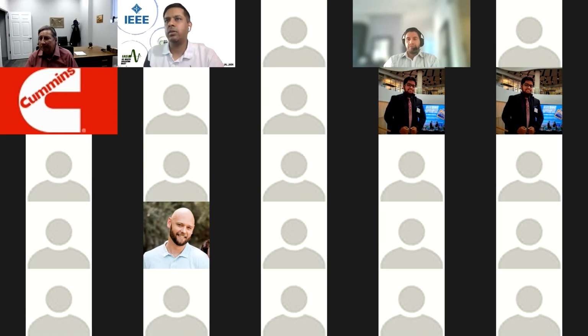Yeah, I have one comment from Mr. Matsuda again. He said, while passive filters are low cost, their LC component is fixed, usually tuned to 100% speed of the VFD/motor. Active harmonic filters are higher cost, but they mitigate harmonics through all loading or speed combinations and provide power factor correction. Okay, good question. I think I understand some of what he's looking at there. Truly, an active harmonic filter does cover the load range very effectively. Obviously, in the very lowest ranges you've got a little bit of losses with fans and those kinds of things, but you're only injecting the amount of current that you need, and they're very, very efficient.